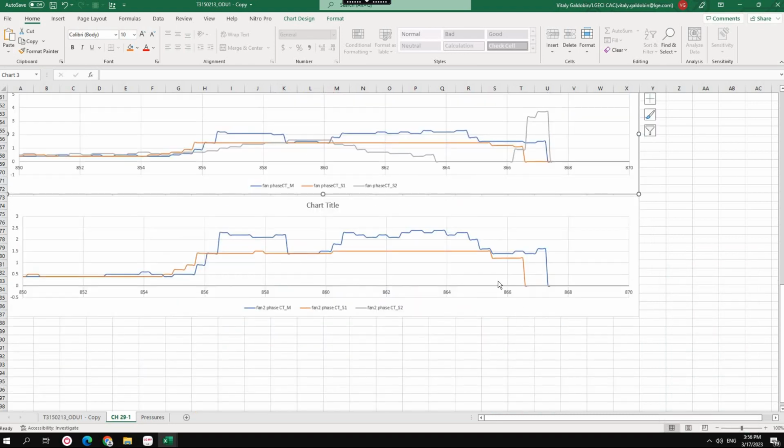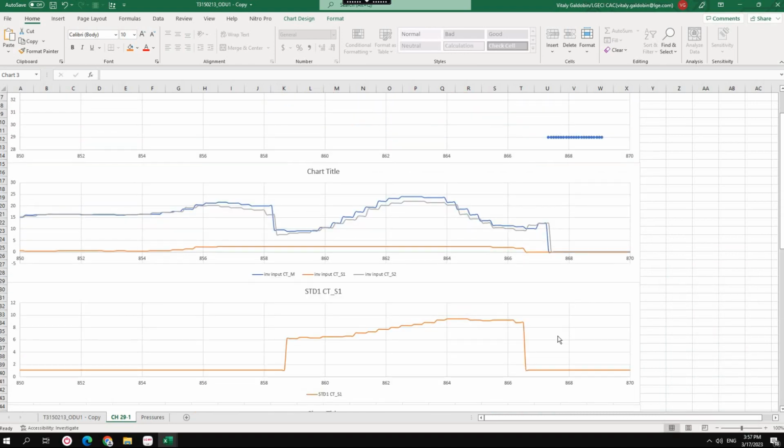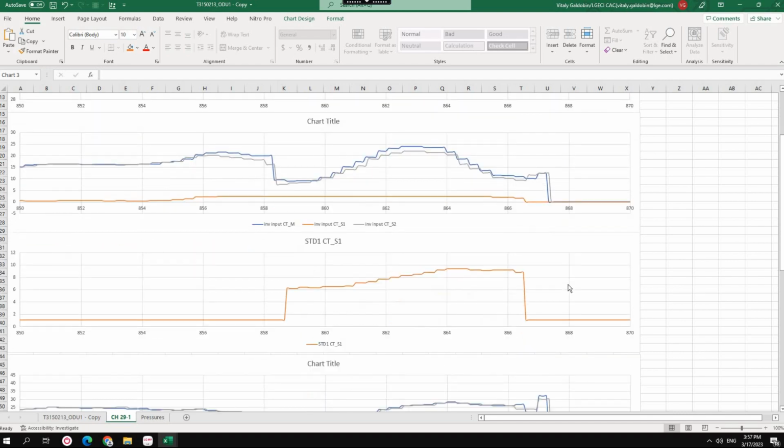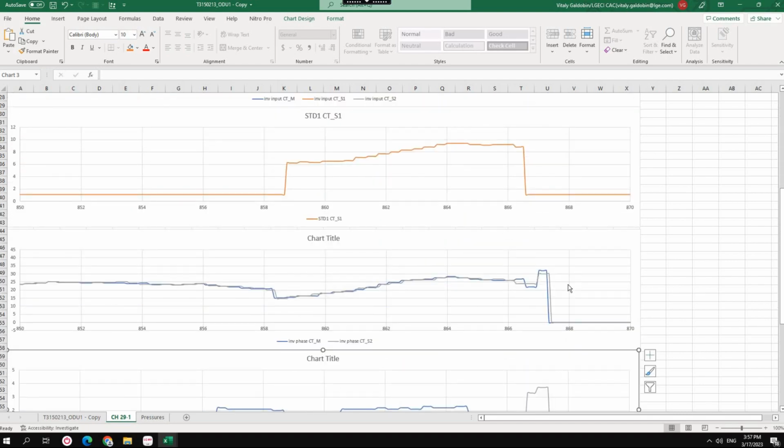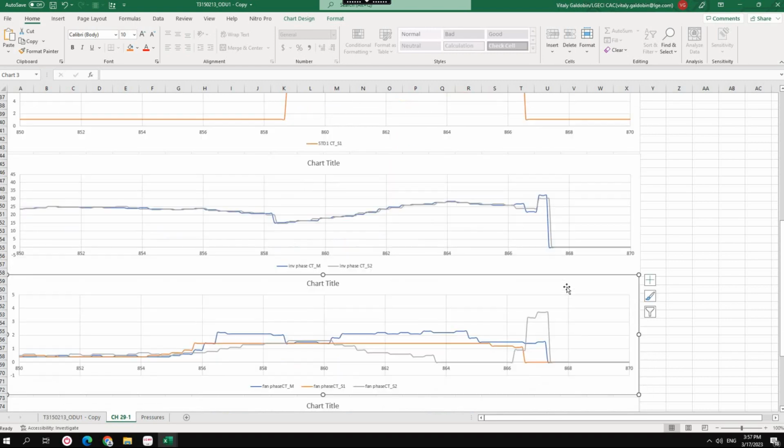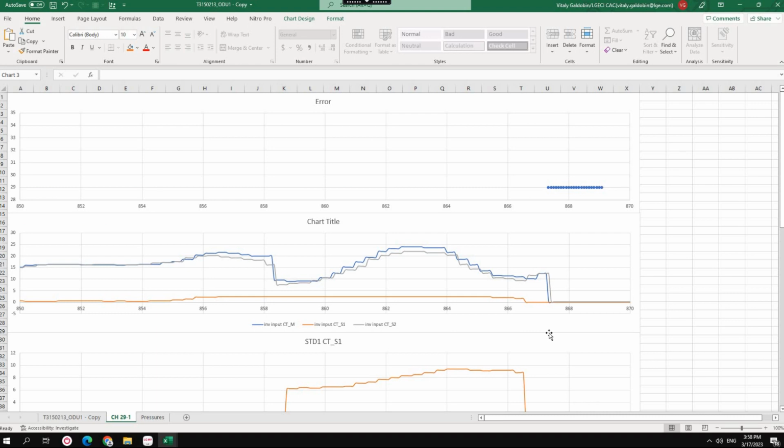Based on all this information, I would go with standard procedure of checking diode bridge and inverter board on master unit, and need to check fan motor on slave 2 unit with its board. Once again, this kind of situations you cannot spot just reviewing the data from LGMV software.